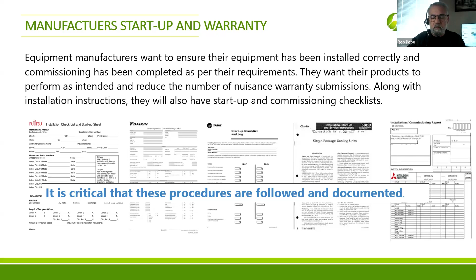There is also a commissioning checklist from the industry, and this is where we see the discrepancies. The manufacturers are only concerned about their equipment operating adequately to ensure there's no failures in major components like fans, compressors, and so forth—installed to a standard contained within the equipment itself. If the equipment is functioning, they don't know the heat load of the house it's living in, or the performance expectations. They're focused on their equipment, and that's where the discrepancy exists.